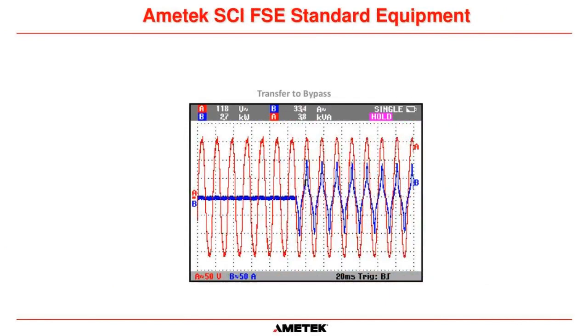And one of the most interesting readings that we take with the oscilloscope is the transfer from inverter to bypass and from bypass back to inverter. Okay, so what we do is we put an amp clamp on the bypass input to the static switch. So when the UPS is running on inverter, there is no current flowing into the bypass, and that is what this blue waveform is here. You can see there's no current. The red waveform you are looking at here is connected to the output voltage of the UPS.